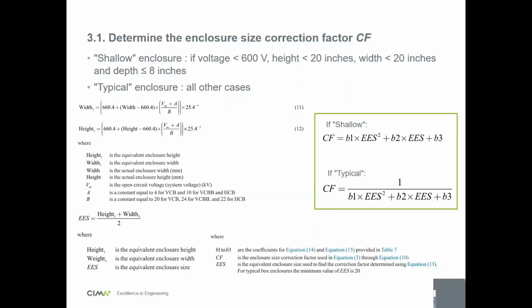So the enclosure size: height, width, and depth. If your voltage is below 600 volts, and your height is below 20 inch, and your width is below 20 inch, and your depth is below or equal to 8 inch, your box is considered shallow. So this will affect the results. If your box is considered shallow, if it respects these 4 criteria, it has an impact on the results. And if it's not shallow, then it's typical.